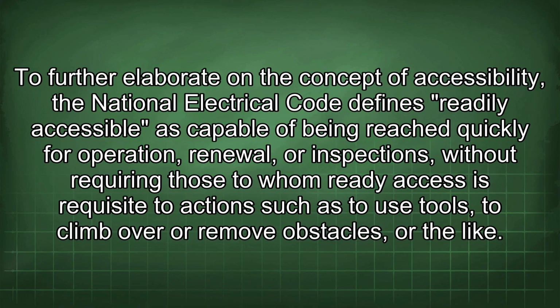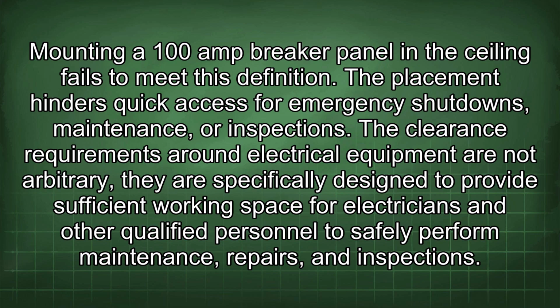To further elaborate on the concept of accessibility, the National Electrical Code defines readily accessible as capable of being reached quickly for operation, renewal, or inspections, without requiring those to whom ready access is requisite to take actions such as to use tools, to climb over or remove obstacles, or the like. Mounting a 100 amp breaker panel in the ceiling fails to meet this definition. The placement hinders quick access for emergency shutdowns, maintenance, or inspections.